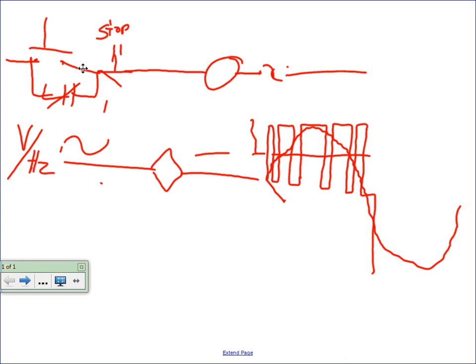Drive, we can soft ramp it, but then we can also control the speed of the motor at any frequency we want. So why do we do it in fans or HVAC systems? They used to use a full voltage starter and run that motor at full speed and then use dampers to control how much volume actually gets through the ductwork. So that's like driving your car with the accelerator all the way to the floor and using your brake to control the speed. You're wasting tons of energy.